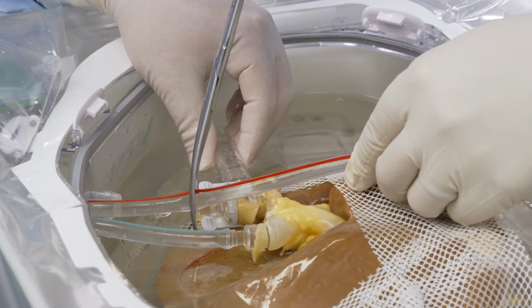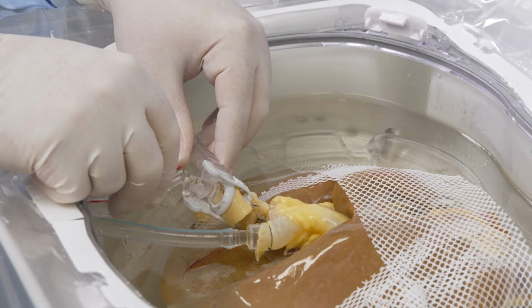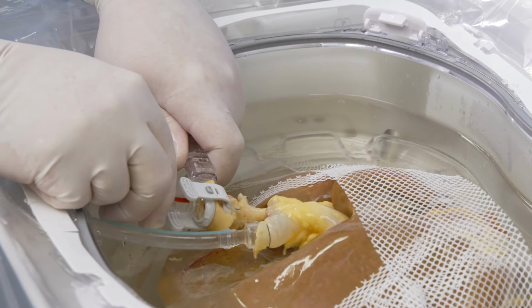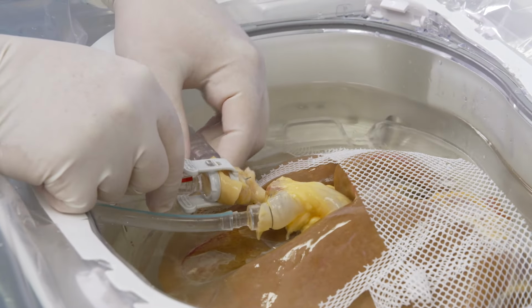If the lines are too long, there is a potential for suboptimal perfusion caused by a kink of the vasculature. If the lines are cut too short, there is potential for increased stress to the vasculature.